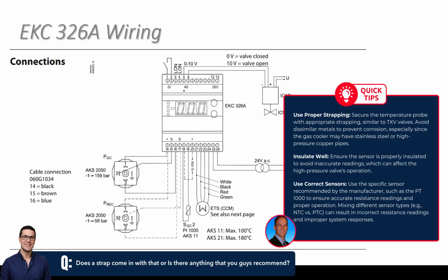So they're using those 10K things, or a microthermal one, different than the PT1000. And it has to be the specific one that Danfoss sells as well, I believe, because I've seen it where the NTC, they're different than the PTC because they're negative temperature coefficient, but they have different resistance charts. So one reacts faster than the other. So if you don't use the correct one, you could be getting the wrong resistance into the controller.